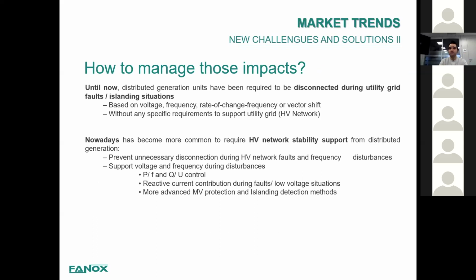How to manage those impacts? Until now, the distributed generation unit has been required to disconnect during utility grid faults. That means if there is a disturbance in the frequency or in the voltage of the HV or MV network, these renewable sources were required to disconnect, leave the traditional power plants to recover control of the network, and after that, connect to the network again.